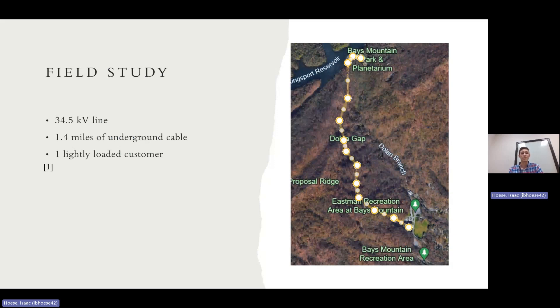So it fits all criteria for ferroresonance to occur. And what happened in this scenario is two hydraulic reclosers that were located at the tap, so where it first went underground, got blown off the pole. And we'll see why in just a few minutes.